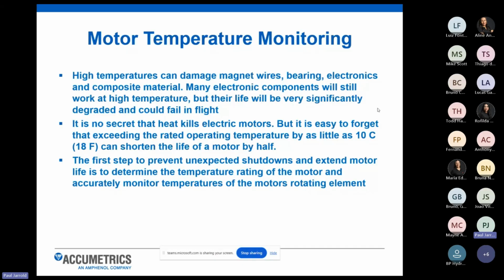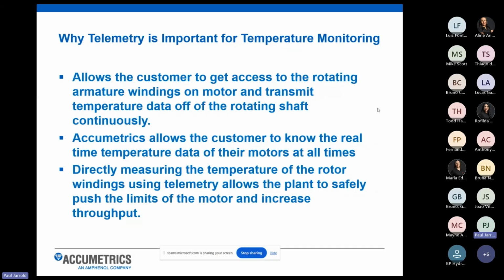And over time, that can cause significant damage and basically cut your motor's life expectancy in half. So it's very critical to know if you're getting hot spots inside of the motor and be able to monitor for that. So our system allows, again, the customer to gain access to the rotating armature windings of a motor, to detect those transient temperature spikes or hot spots inside of the armature winding. It gives you real-time temperature data off these motors at all times.